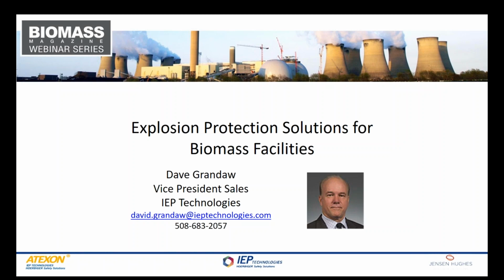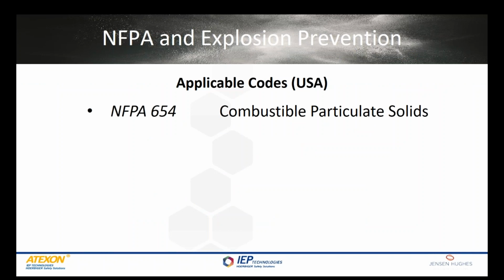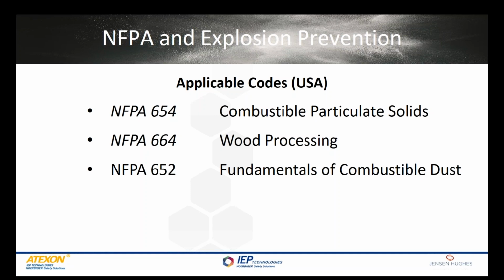There are unusual circumstances that occur which do result in actual explosions within vessels. Because of that, there are NFPA standards that do require the use of explosion protection systems of some sort. The standards that we're talking about specifically would be NFPA 654, which is for the manufacturing, processing, and handling of combustible particulate solids; NFPA 664, which is for wood processing; and NFPA 652, a relatively new standard called the Fundamentals of Combustible Dust, which creates the foundation that all of the other industry-specific standards are trying to invoke.